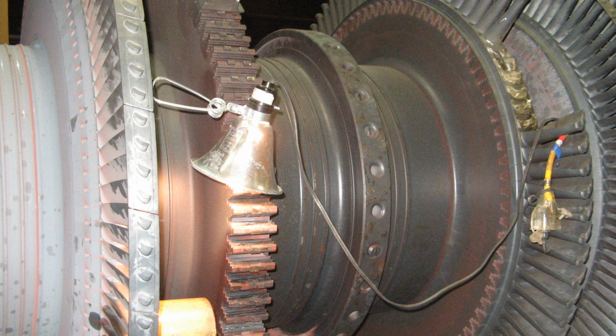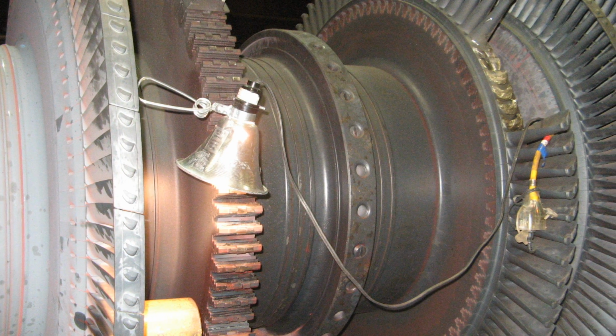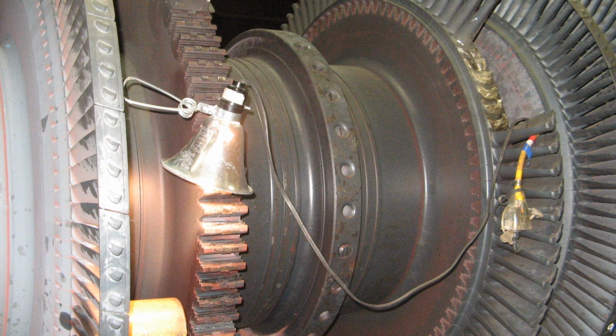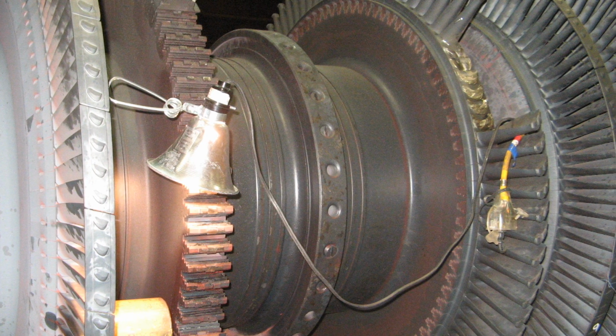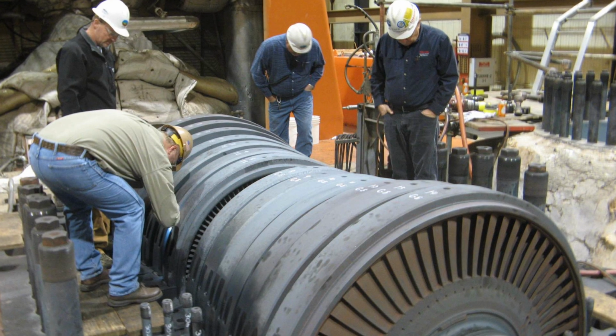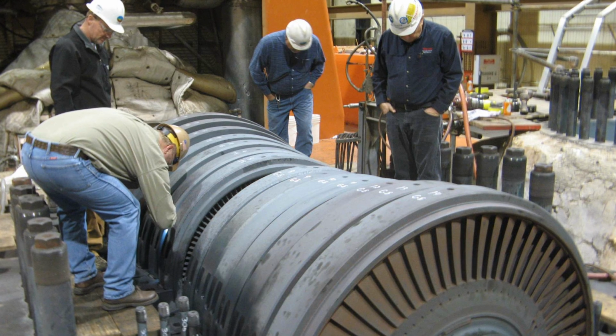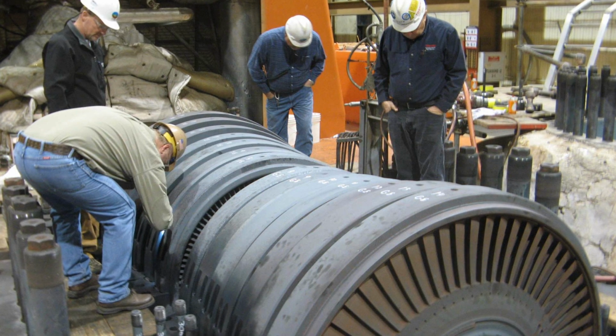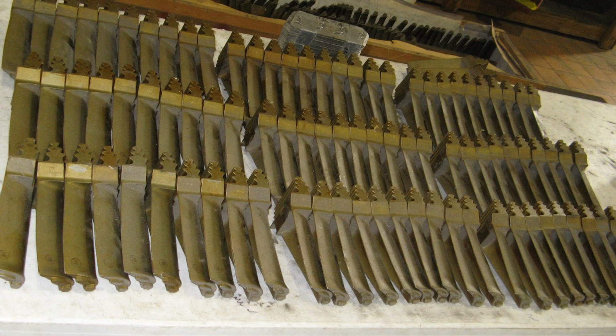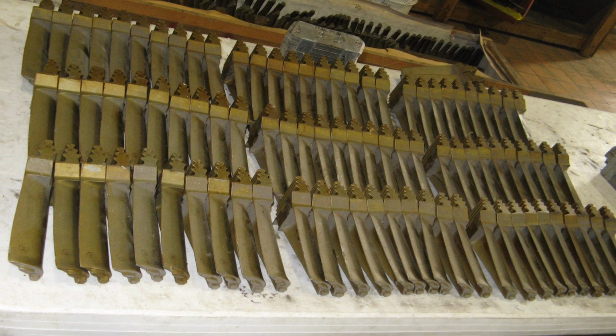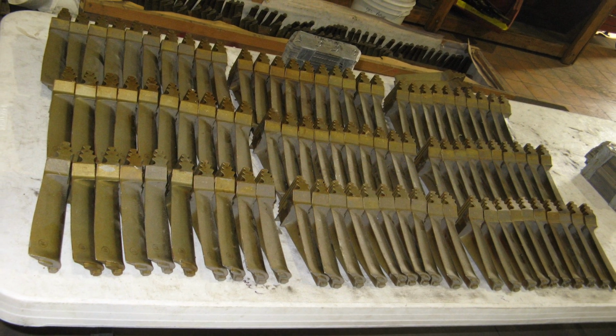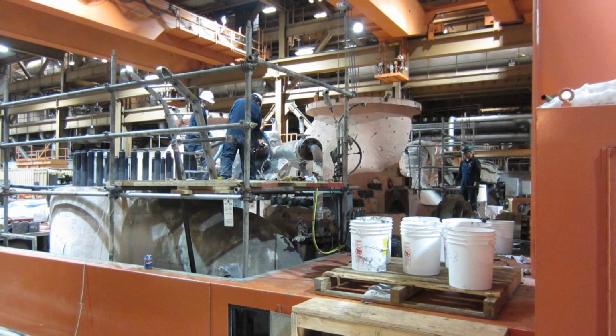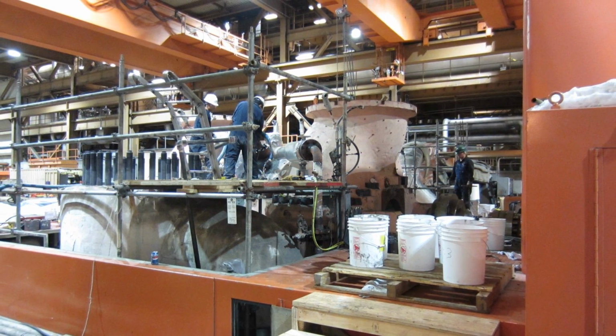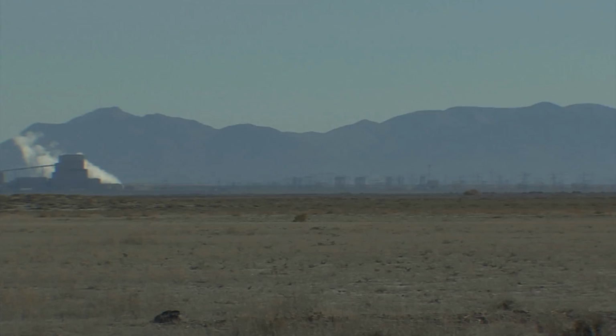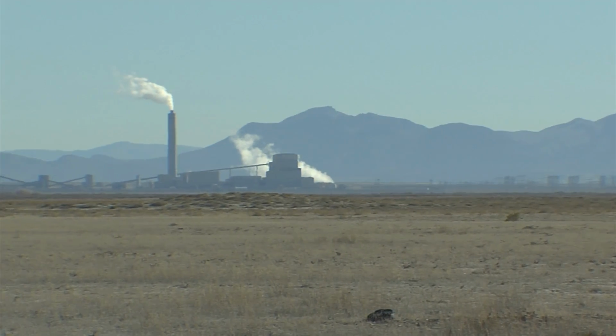Bucket covers eroded from the steam flow side, pushing up or angel winging the outer portion of the cover. The cover then caught the spill strip of the diaphragm, which rolled out both the bucket covers and spill strips, and also caused downstream damage as failed components went through the turbine steam path. The IP turbine 8th stage buckets on both the turbine end and the generator end were replaced. The IP turbine 8th, 9th, and 10th stage bucket covers on both the turbine end and the generator end were also replaced.